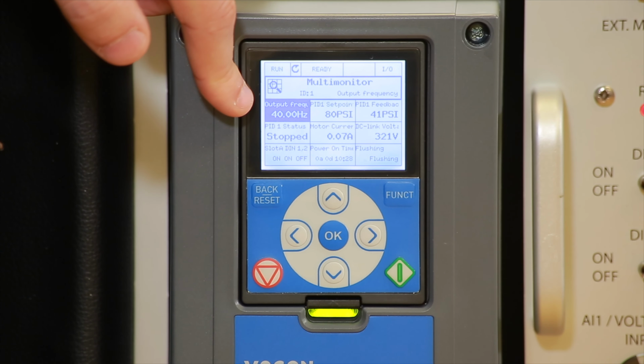Also, this drive can run multi-pump control applications, such as one drive can operate and control up to 8 motors. Let me repeat that. One drive can control up to 8 motors. We have a choice with one drive and 7 starters maximum, or one drive and 7 soft starters, or we can have 8 drives altogether, anywhere from 1 to 8. So this is called the multi-pump single drive if we have starters or soft starters, or multi-pump multi-drive if we have multiple drives. For this case scenario, we're going to go with the simple application of PID control of one drive and one pressure transducer. So we're going to go OK.